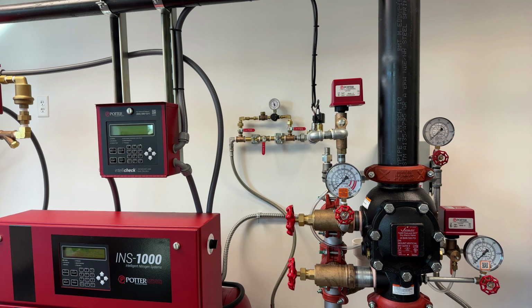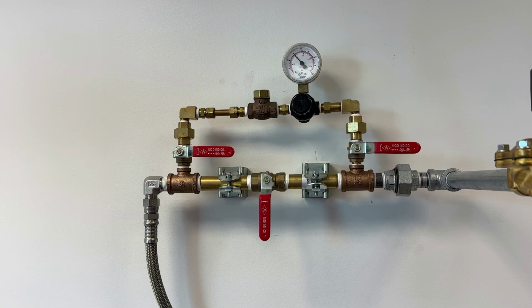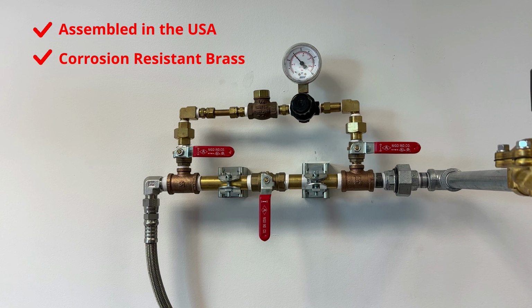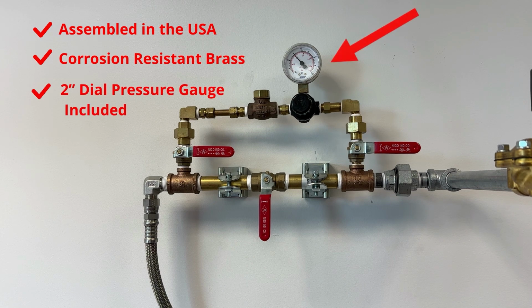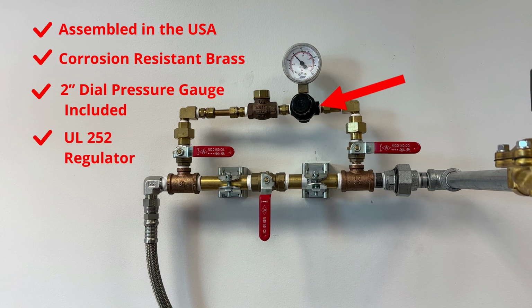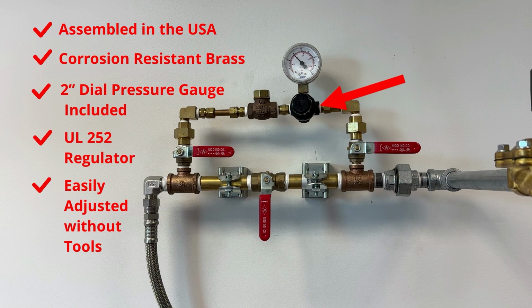When the sprinkler system operates in a fire situation, the sudden loss of pressure overcomes the AAMD's ability to replace the lost nitrogen or air through a 3/32 restricted orifice, allowing the valve to open as intended. The Potter AAMD is assembled in the USA using corrosion-resistant all-brass construction. It comes with a custom high-resolution 2-inch dial pressure gauge to ensure accuracy, while the adjustment knob makes it easy to set the pressure settings on the UL 252 listed regulator without tools.